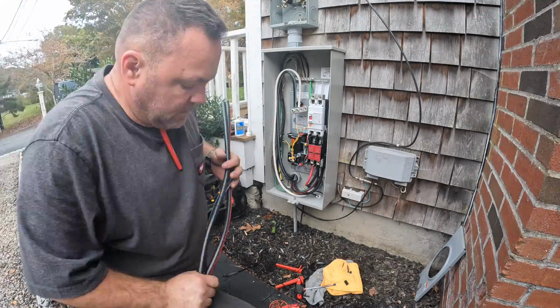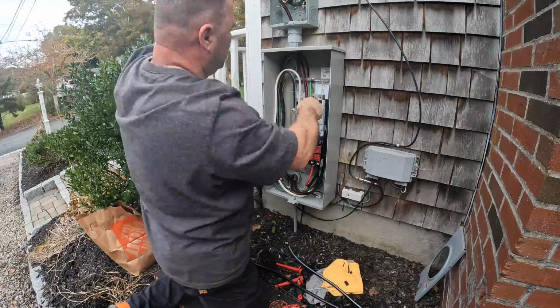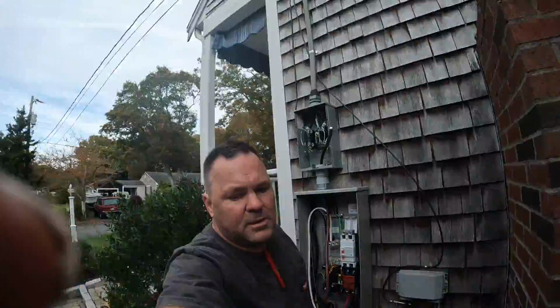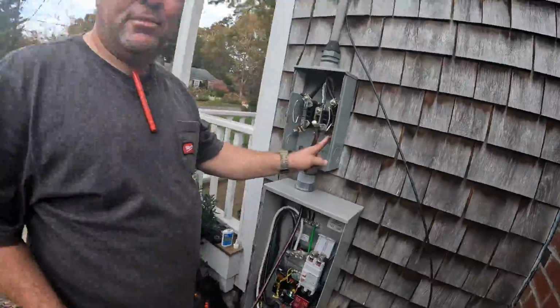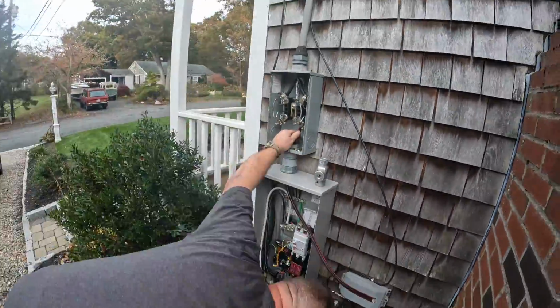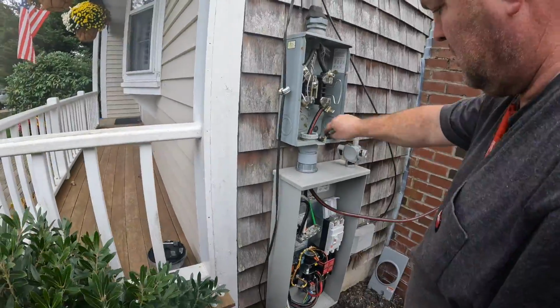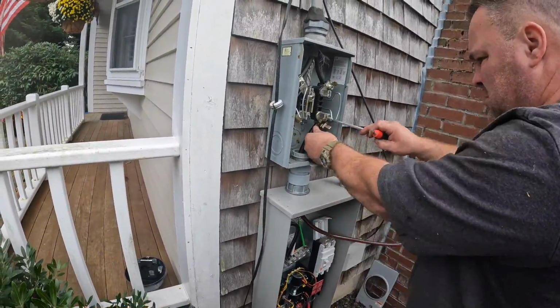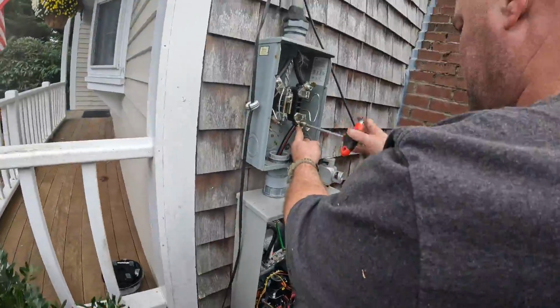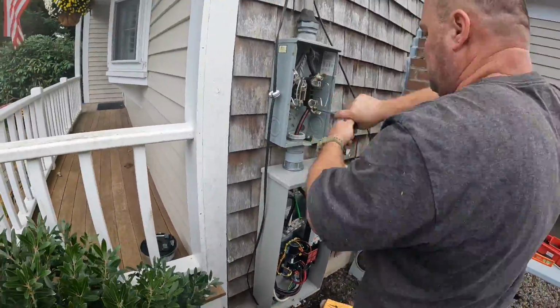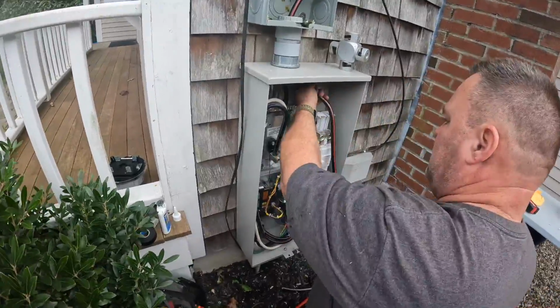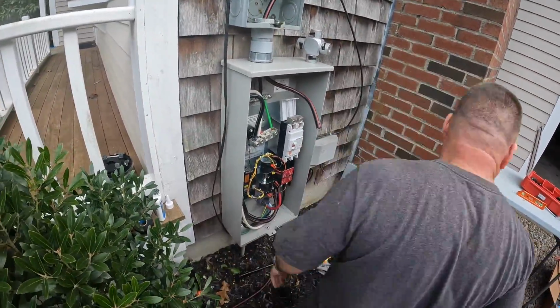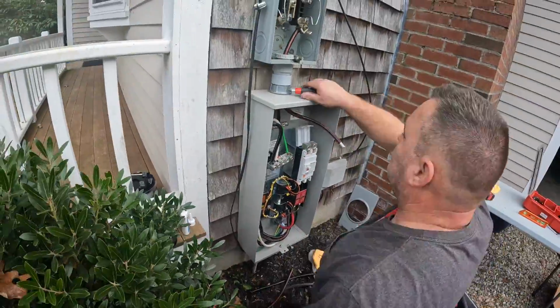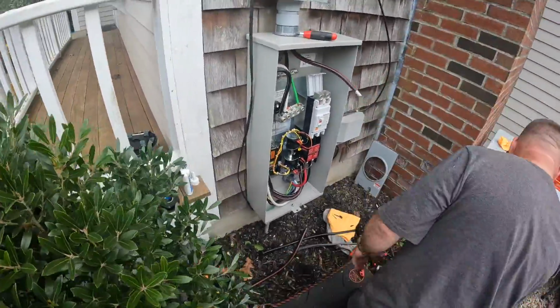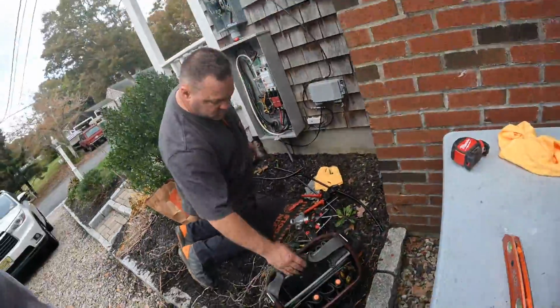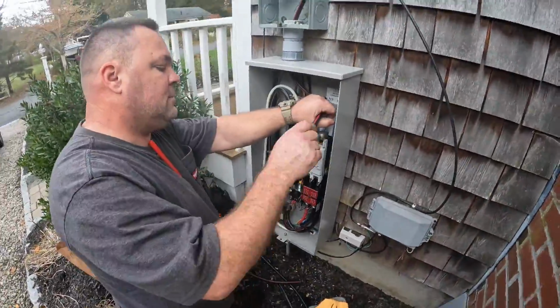Finally, at this point, I'm able to attach the final conductors to the load side of the meter. Now, you've got to be careful. Inside that meter on the line side, there's live power, and you've got to be careful not to hit that stuff. What I found is to terminate at the meter first, and then work your wires inside the larger enclosure below, because you have more room to adjust your conductors into those terminals. This is 4/0 aluminum, and if you've worked with this before, you know it's not the simplest wire to manipulate and bend. So the more room that you have, the easier it will be to bend that conductor, which is why I terminate inside the transfer switch second.